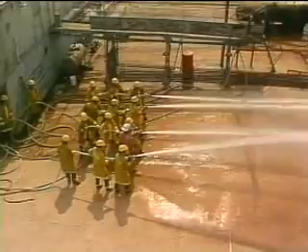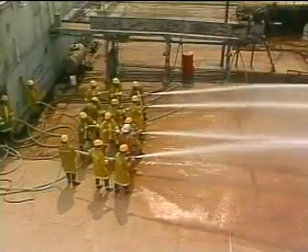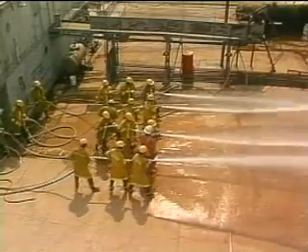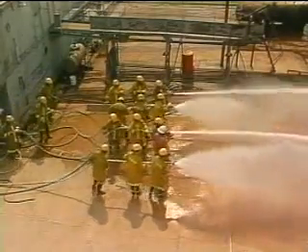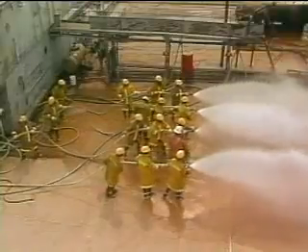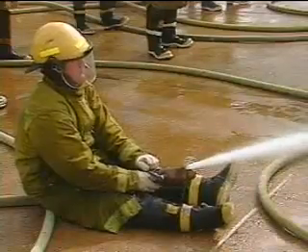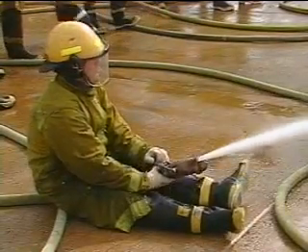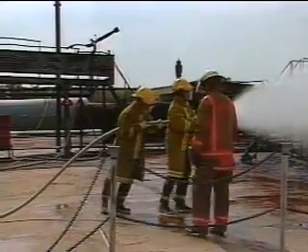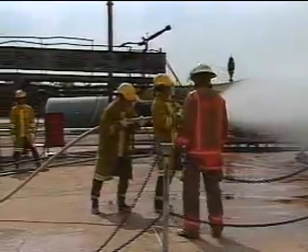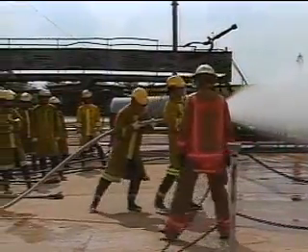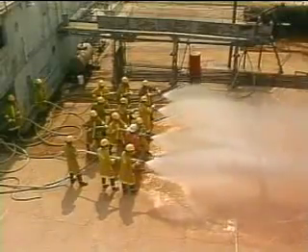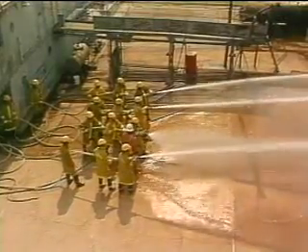We've just seen a typical hose team using a 2.5-inch line. Let's look at a team using a 1.5-inch line. 1.5-inch hose lines require less manpower and they're easier to use. Generally speaking, one person can handle a 1.5-inch line if it remains stationary. However, a team of at least 2 persons is required if the hose line must be moved around, which is generally the case. In any case, the nozzleman always controls the nozzle and gives the commands.